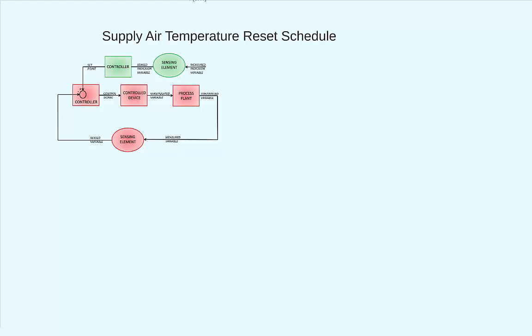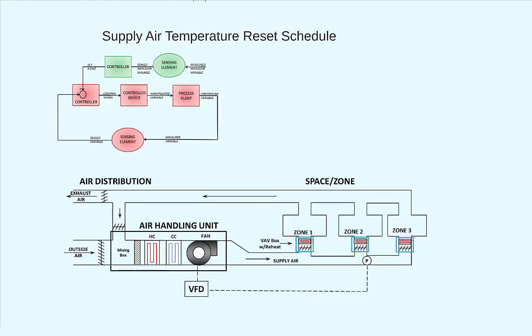So let's review what we mean by a reset schedule again. A reset schedule is basically a schedule which changes the set point in a closed control loop based off of some other variable. You will often hear the term supply air temperature reset schedule when talking about all sorts of different air system configurations, to include the VAV with reheat configuration we have been discussing. But let's be clear. The supply air temperature they are referring to here is the temperature of the air coming out of the air handling unit, not necessarily the temperature of the air being supplied to each zone, as that will vary depending if the reheat coil is engaged or not.